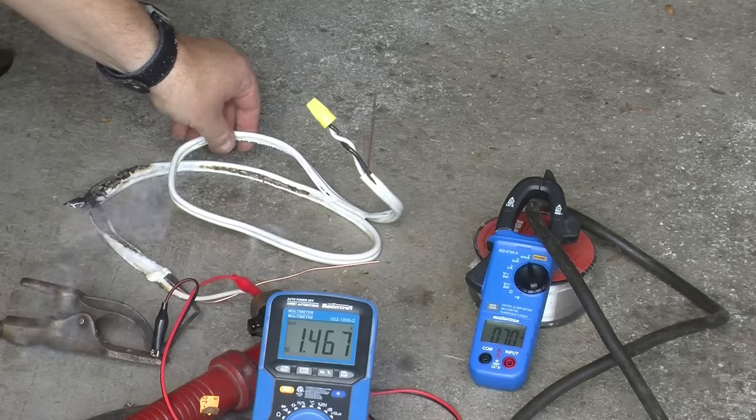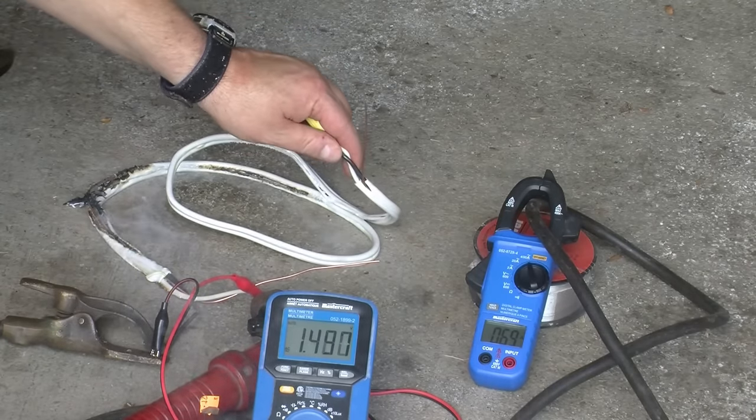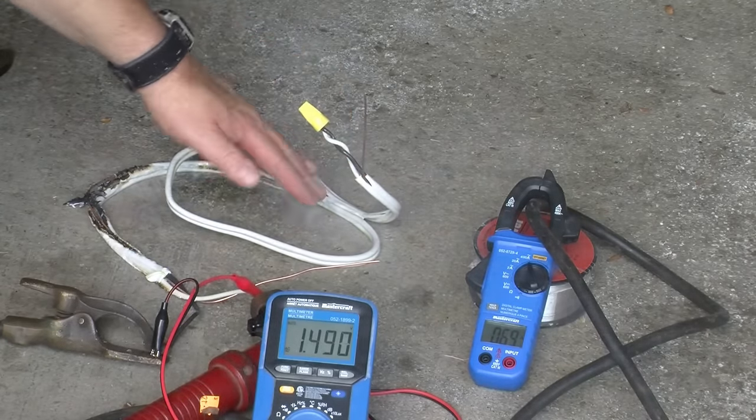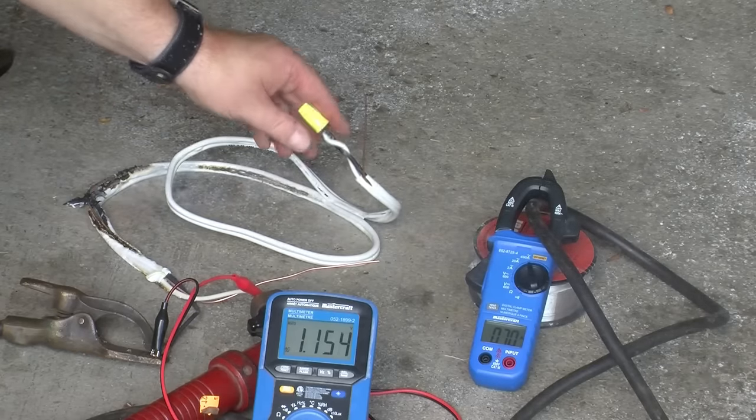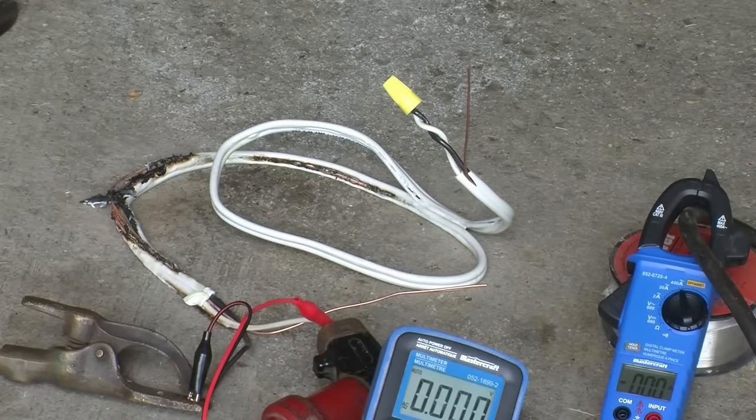Although it may be too late — this section isn't that hot, so we've got a short somewhere in here. I would have liked to test the Marr connector itself; we'll do that separately. Let's see what happens if the breakers don't trip and you get a couple of hundred amps through 14-2. Here goes.